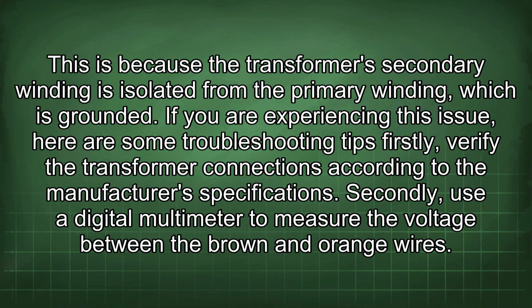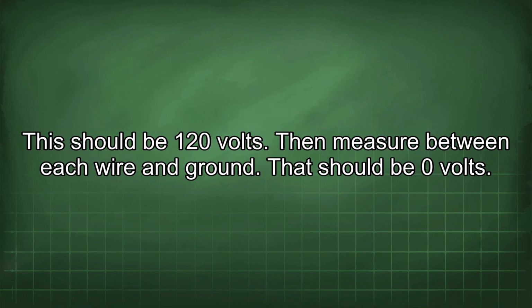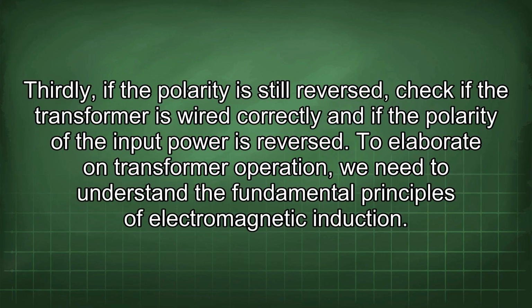If you are experiencing this issue, here are some troubleshooting tips. Firstly, verify the transformer connections according to the manufacturer's specifications. Secondly, use a digital multimeter to measure the voltage between the brown and orange wires. This should be 120 volts. Then measure between each wire and ground. That should be 0 volts.